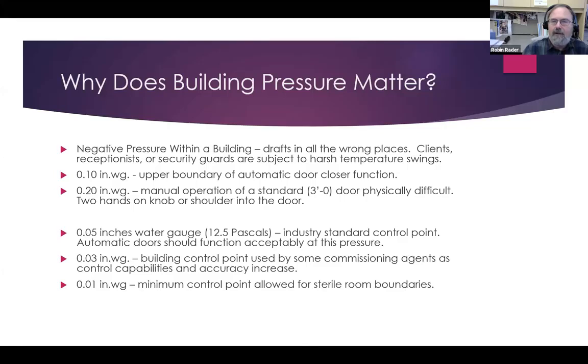At a 0.20 inch static pressure, manual operation of a standard 3/0 door is physically difficult, requiring 2 hands on the knob to pull it closed or a shoulder to push it open. The 0.05 inch water gauge pressure is the industry standard control point for building static pressure. At that pressure, automatic doors function acceptably. Some commissioning agents are setting building static pressure now at 0.03 inches water gauge, which is feasible because of the increased accuracy of our differential pressure sensors. Just for reference, 0.01 inch water gauge is the minimum control point allowed for sterile room boundaries.